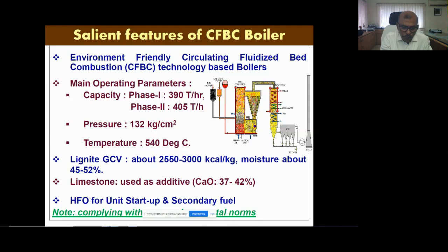Then we are using HFO only for unit startup or as a secondary fuel, sometimes during part load operation, but it is rarely used for part load. Though these units were commissioned in two phases, the first around 2000 and the second in 2010, we are fully complying with the new environmental norms, with only minor modification and a retrofitting job done in the ESP.